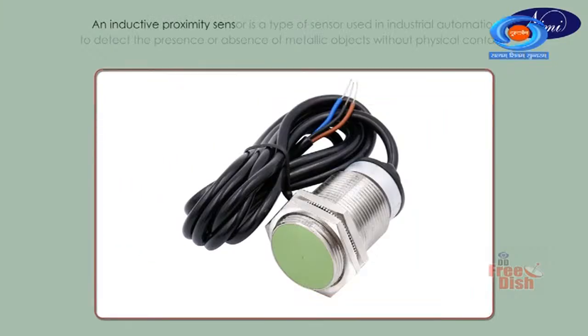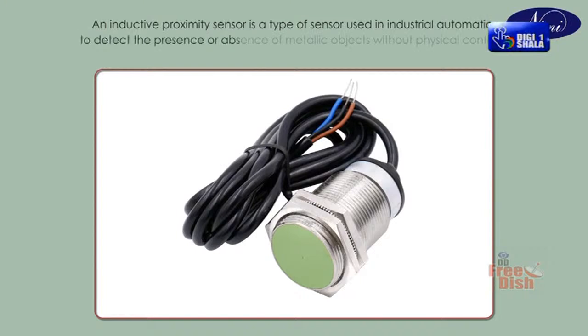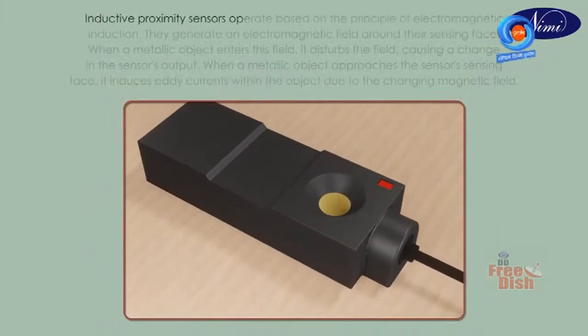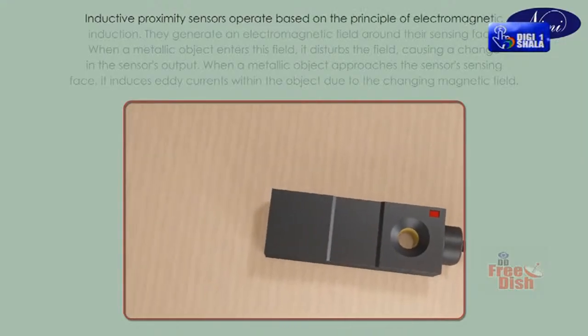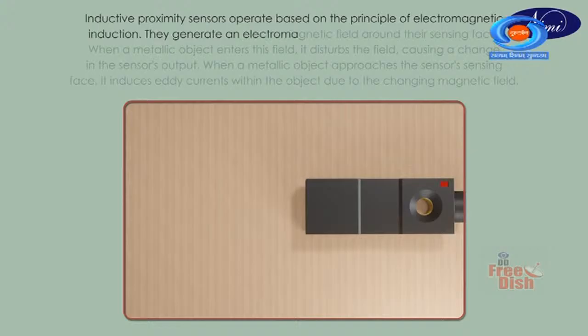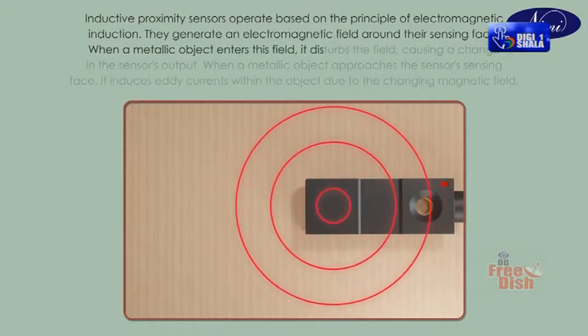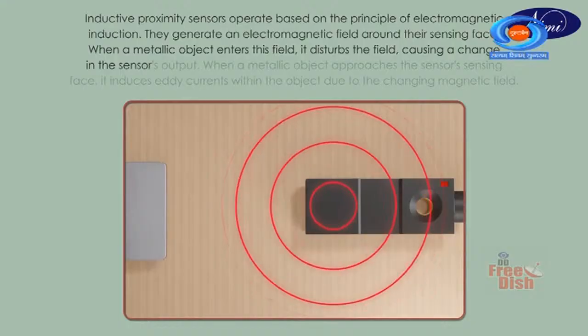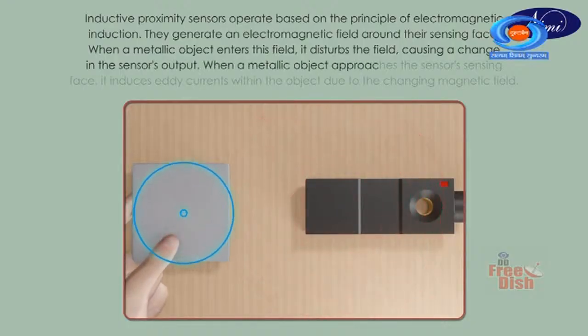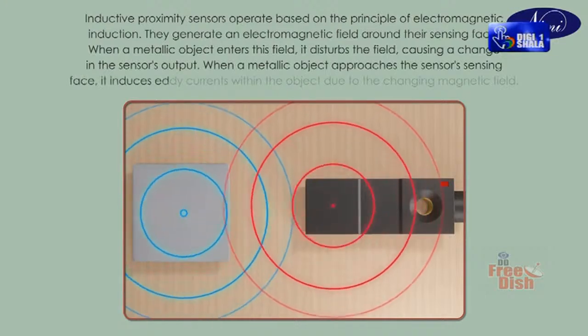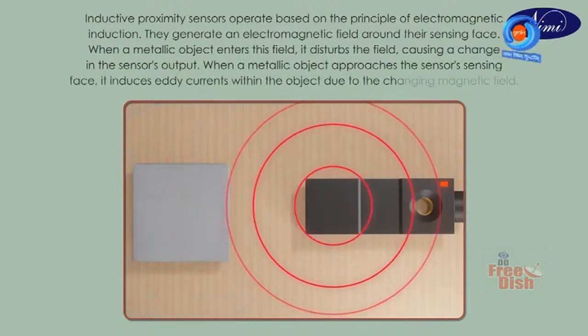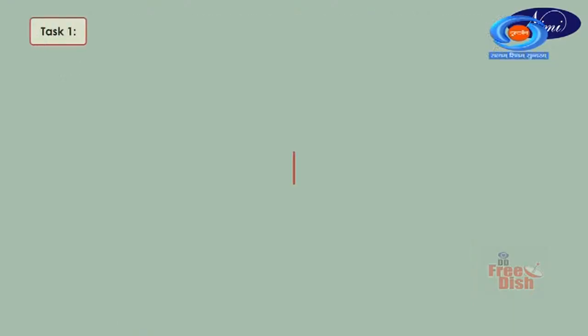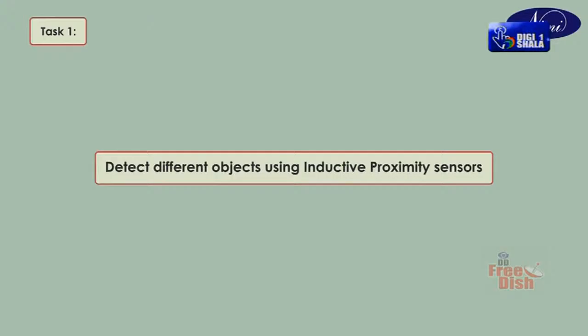Let us discuss inductive proximity sensors. An inductive proximity sensor is a type of sensor used in industrial automation to detect the presence or absence of metallic objects without physical contact. Inductive proximity sensors operate based on the principle of electromagnetic induction. They generate an electromagnetic field around their sensing face. When a metallic object enters this field, it disturbs the field, causing a change in the sensor's output. When a metallic object approaches the sensor's sensing face, it induces eddy currents within the object due to the changing magnetic field.